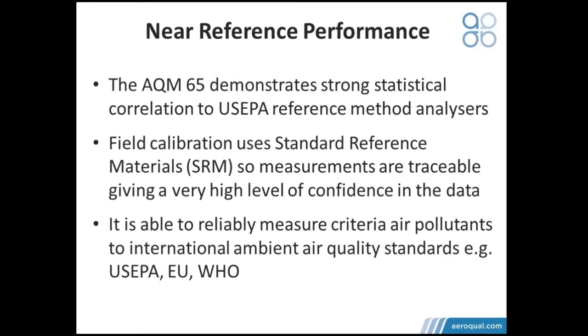The reason we have a very strong statistical correlation is because we primarily use the same standard reference materials for calibration in the field as are used for ambient reference stations. That means the measurement is traceable, even at the point of measurement and at post-validation - traceable to a reference standard. This gives people a high level of confidence in the data. Thirdly, we're able to reliably measure pollutants to most international ambient air quality standards, including the World Health Organization, EU levels, and US EPA national air quality standards.